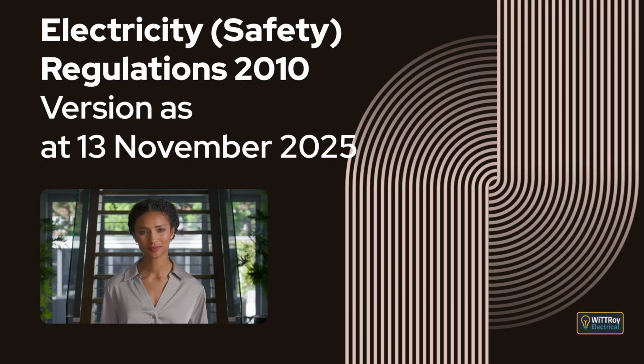It explains that if the installation or part installation was disconnected from the power supply while the work was done, the work is treated as complete only once it is connected or reconnected. The regulation then explains what an electrical safety certificate must contain, including confirmation that the installation is safe to use, whether the certificate applies to the whole installation or only part of it, the location of the installation, the required authentication mark, the date the connection was done, the names and registration details of the person who did the connection and any supervisor, and employer license details where applicable.